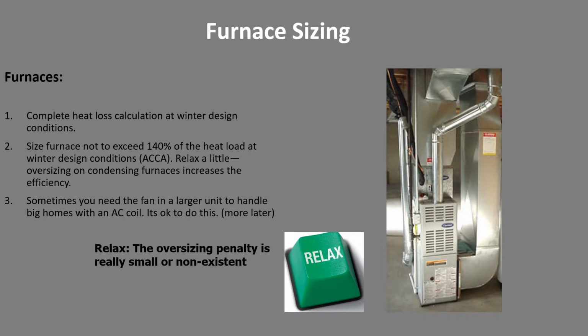On furnace sizing, it's really pretty simple. You calculate the heat loss at winter design conditions. Size the furnace not to exceed 140%. That's ACCA's guideline. In the average new house, the heat loss is about 20,000 BTUs. The smallest furnace you can buy really is 40,000. So you're already twice oversized, and I don't hear too many complaints because of that.